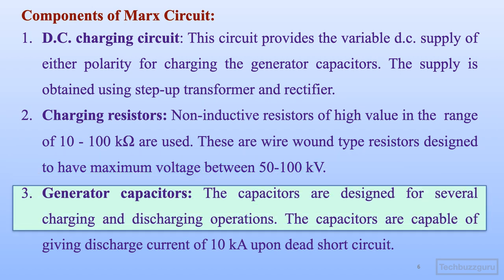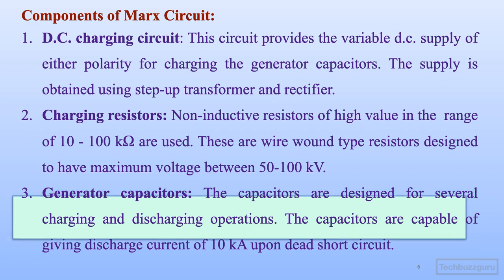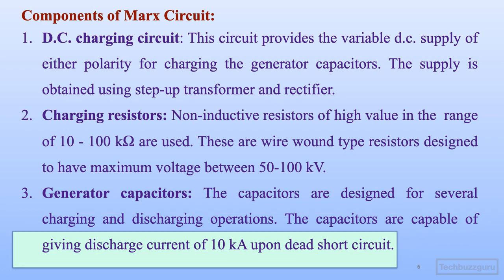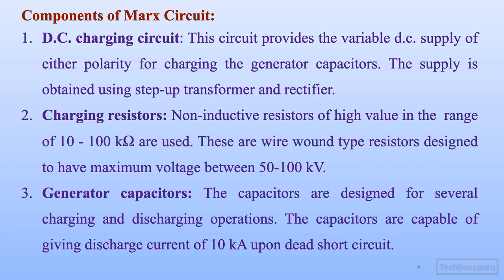The third element of the circuit are the generator capacitors. These are designed for several charging and discharging cycles and are capable of giving a discharge current of 10 kilo-amperes upon dead short circuit. This level of current is usually required for the testing of lightning arrestors or surge absorbers.